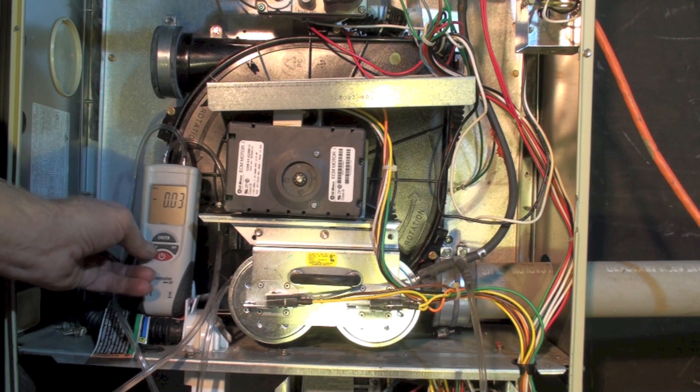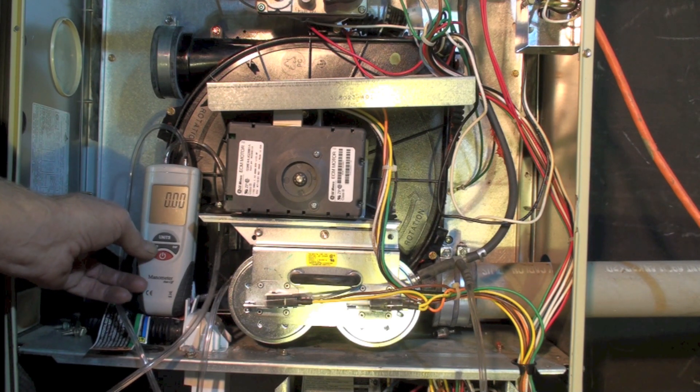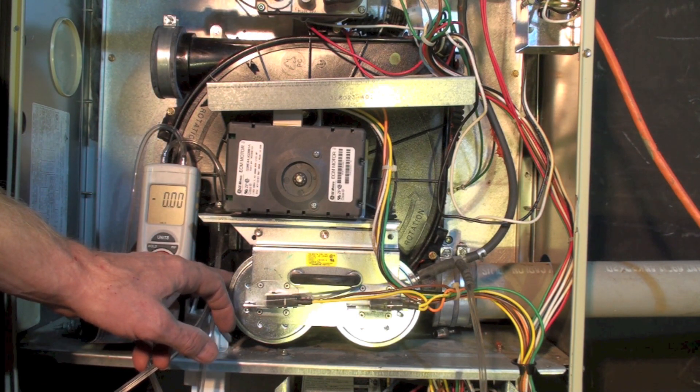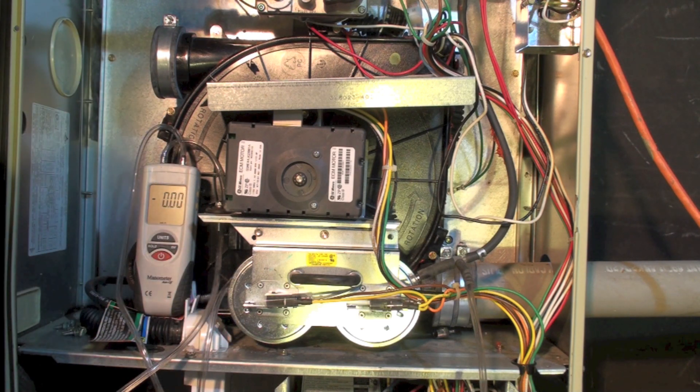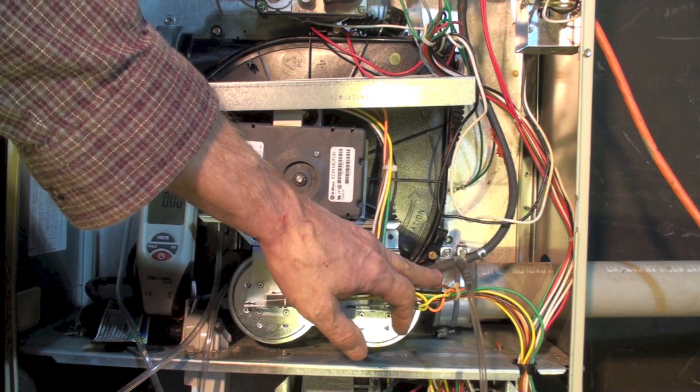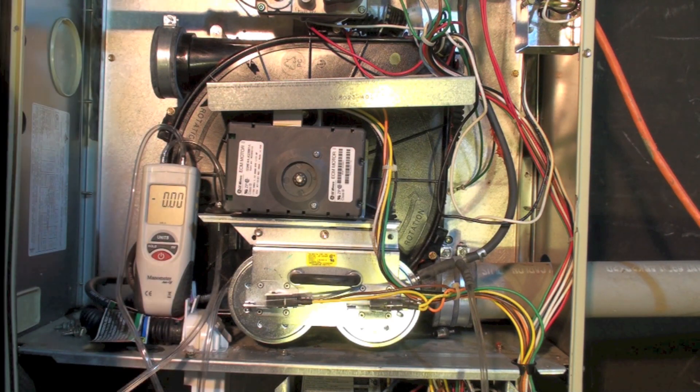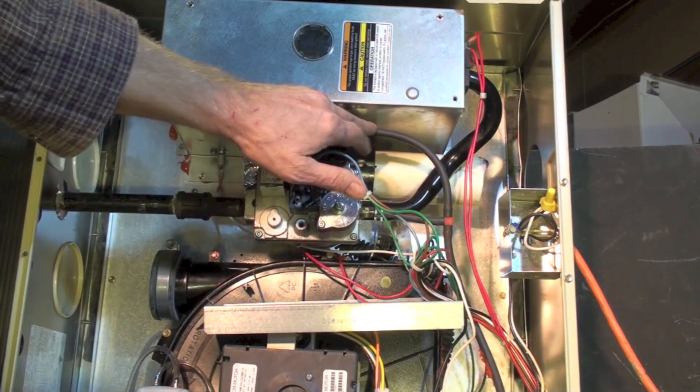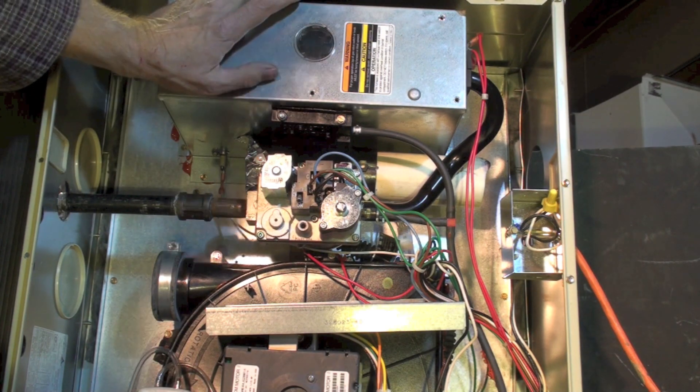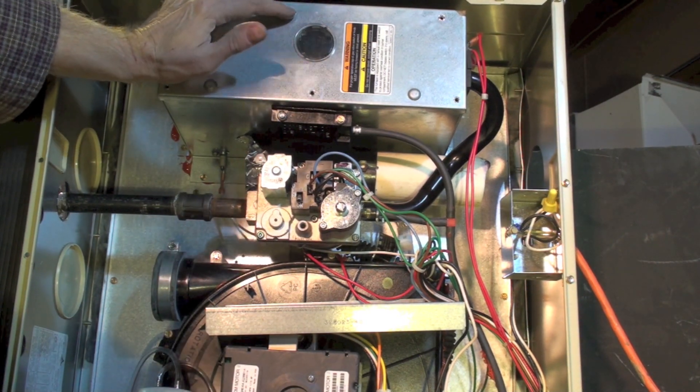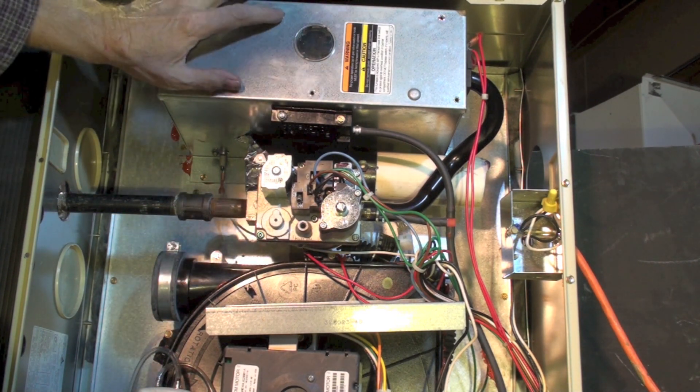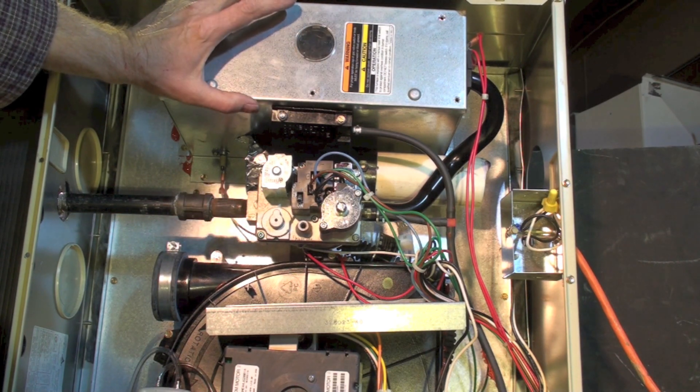Now I'm going to go ahead and zero out this manometer, so it's going to be taking the vacuum that the inducer pulls. The other side of this manometer goes over to here and I put a T in there also. What that's doing is this is a reference for the combustion chamber. It is taking the pressure of the combustion chamber, the negative pressure, and it's working on the opposite side of the pressure switch diaphragm as the pressure coming off the inducer.